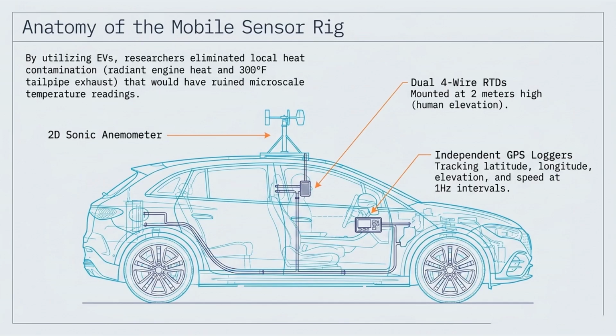How does it solve it? By dedicating two wires purely to supplying a constant electrical current and the other two wires exclusively to measuring the voltage drop across the platinum element. Oh wow, yeah, the system mathematically cancels out the resistance of the lead wires entirely. That is so elegant. And that is how the ASU team was able to achieve an accuracy rating within one tenth of a degree Celsius, right?